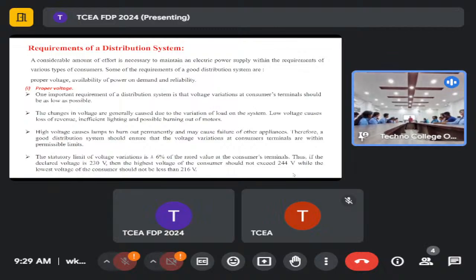If you purchase a bulb of 230 and that bulb is subjected to 250 volts all along, its lifespan will gradually go down, because 230 plus 6%, how much does it come? 230 plus 6% is 244. So 250 is more than 6% above. This is very important. So there are two types of voltage regulation. If we get less than 216 volts, the machine lifespan will also decrease.